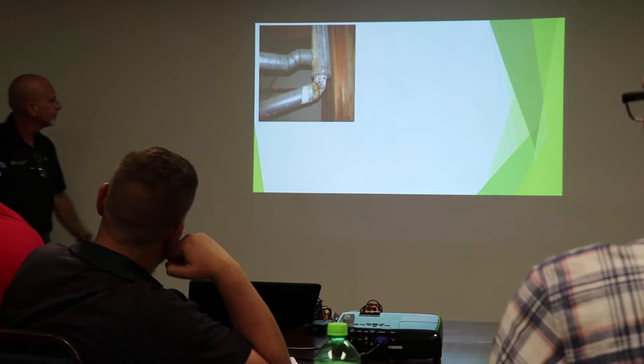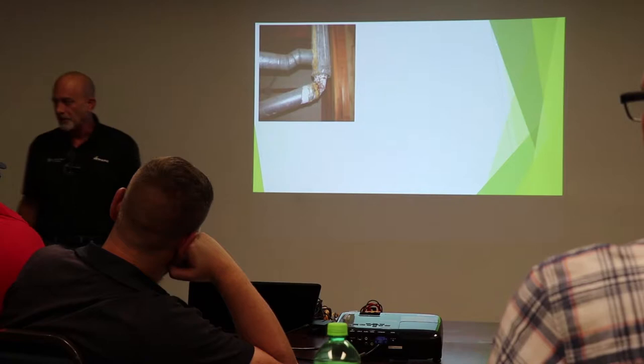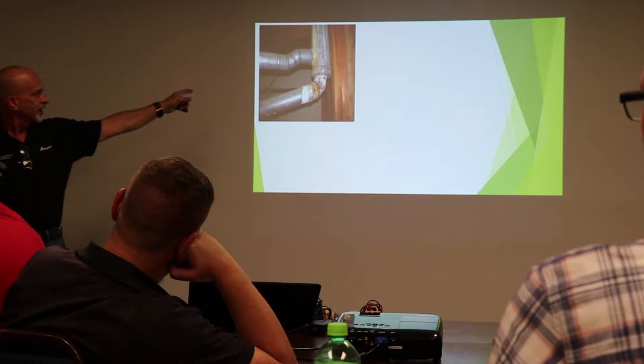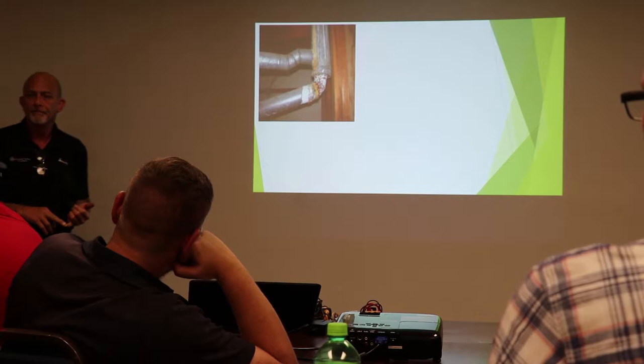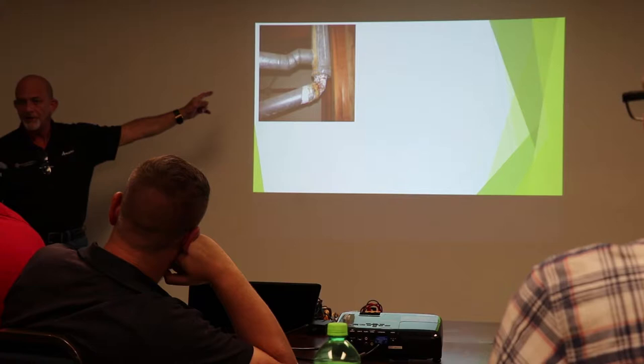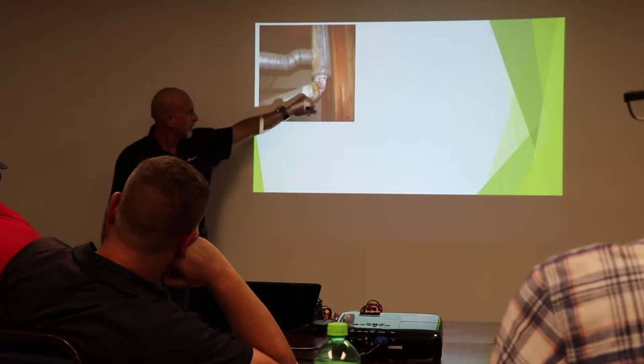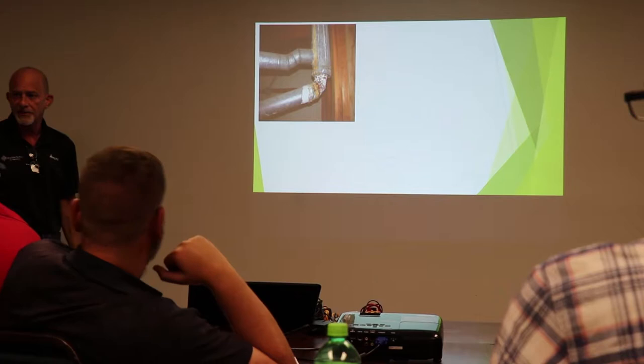All right, our vent pipe. That's an 80% furnace, right? What do we got going on here? A little bit of rust. Got a little bit of rust, got a little bit of water. It's condensing. Most likely that one there could be two things. Maybe we're missing a vent cap. Vent cap blew off from years ago. Maybe that goes right into a masonry chimney that wasn't lined. Regardless, this is condensation coming down our flue pipe, and the white is from the moisture going through the galvanizing. It's leaching through the pipe. Same with that one right there.